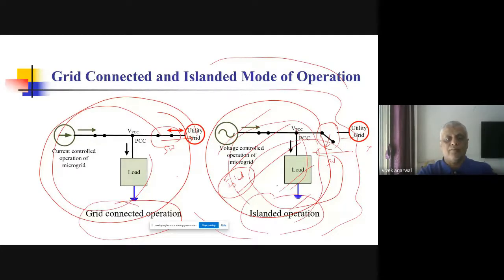The other thing is, you see on the left side, which is the grid-connected case, the utility is connected to the microgrid. So you can see this VPCC voltage and frequency can be directly controlled by the utility grid. The utility grid is huge, so its voltage and frequency hardly change. That is the assumption. They do change a bit, particularly in some countries, including ours, but not much compared to some other smaller systems. So that is what is regulating.